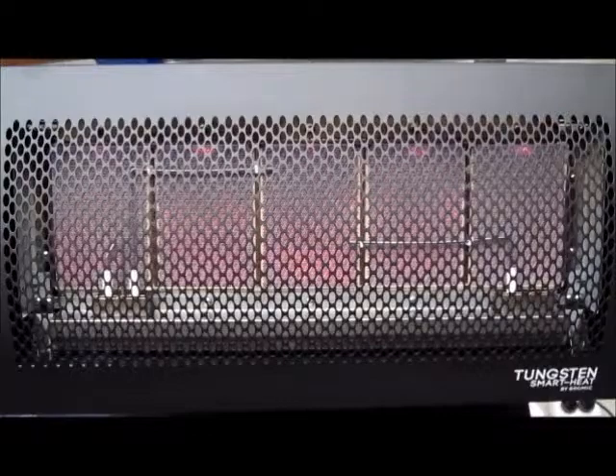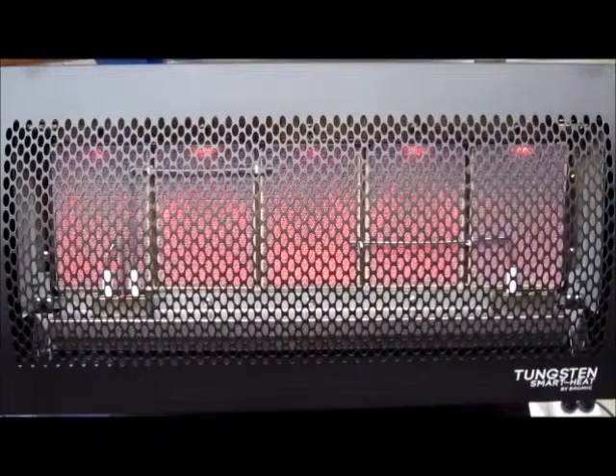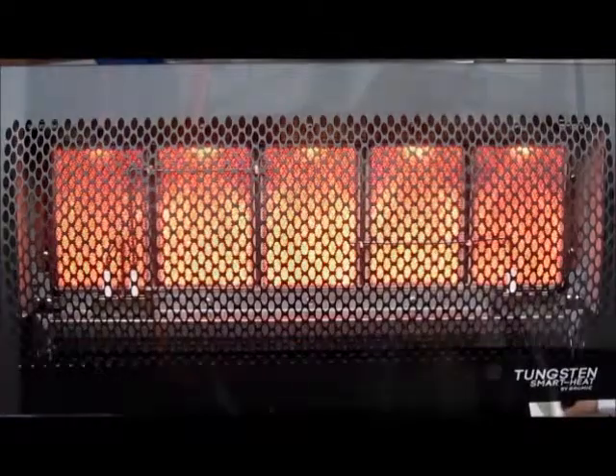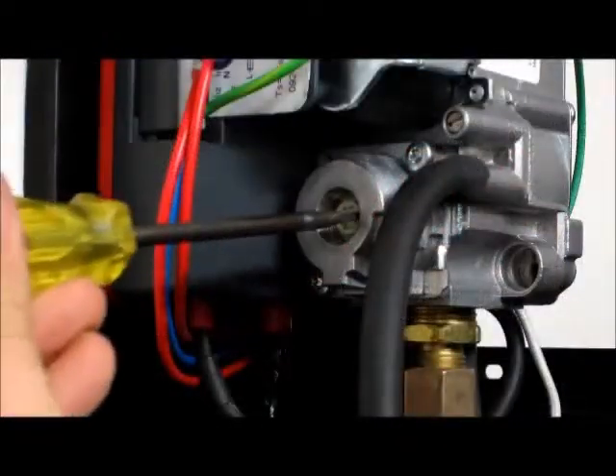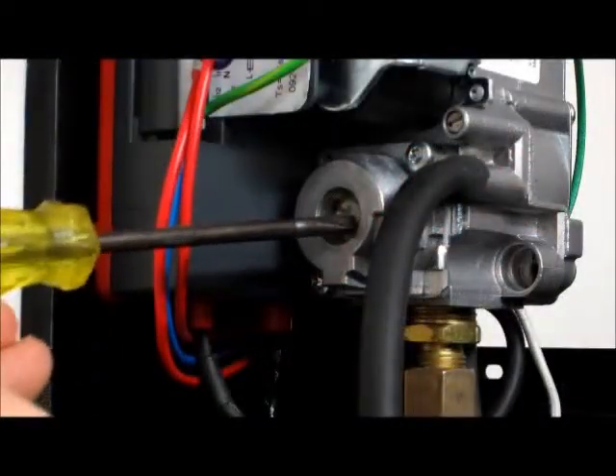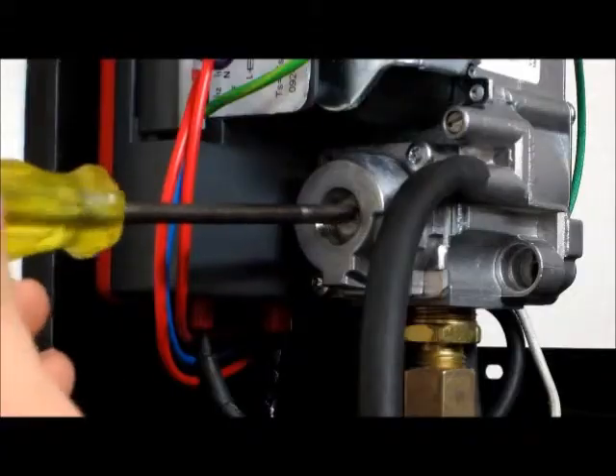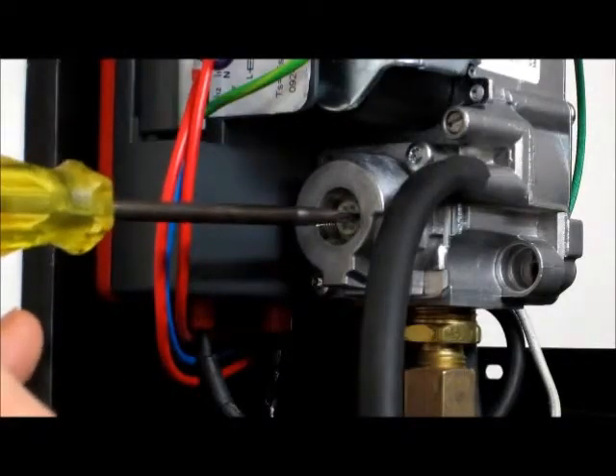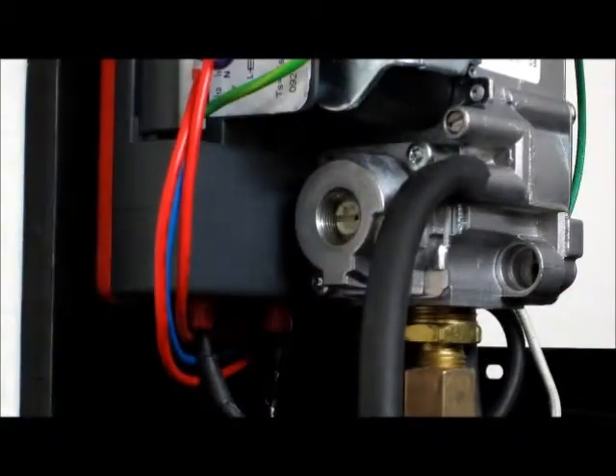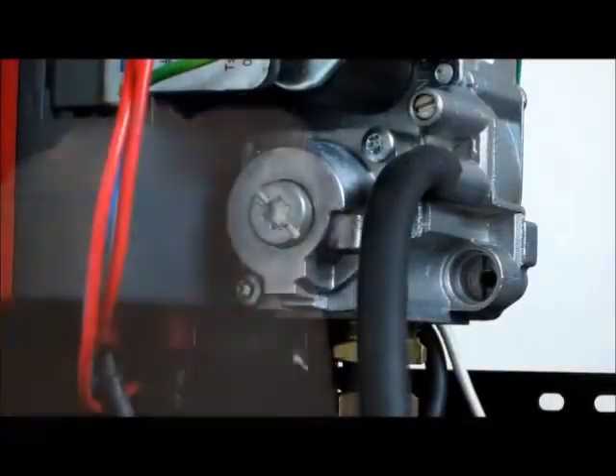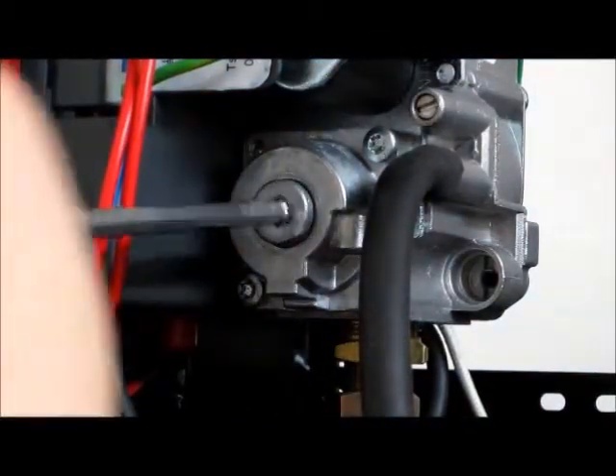Otherwise, the outlet pressure must be set for the appropriate gas type in accordance to your region-specific pressure requirements, as stated in the instruction manual provided with your heater. Ensure regulator cap and outlet test point screw are replaced.